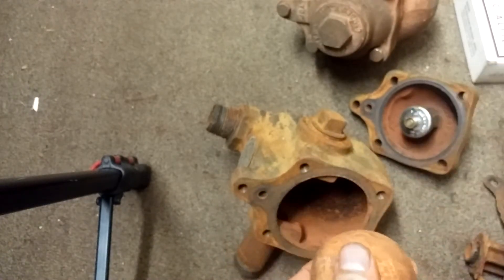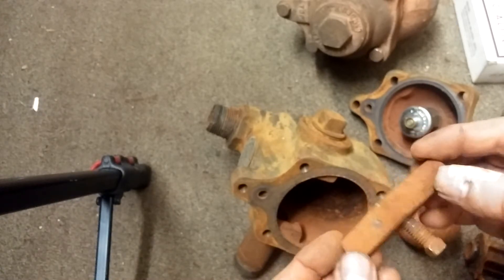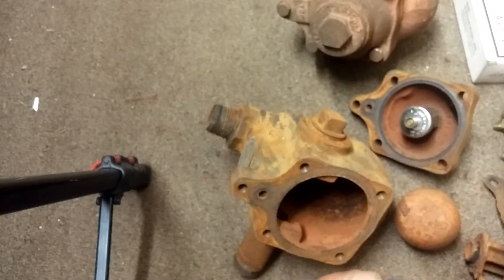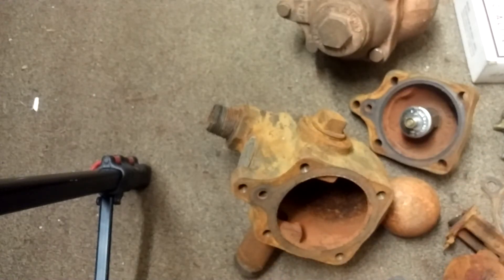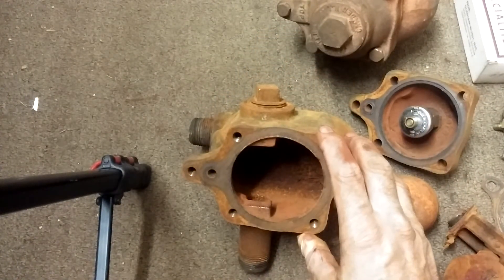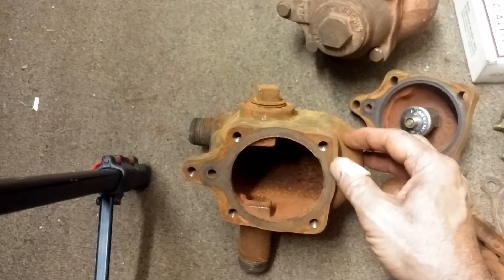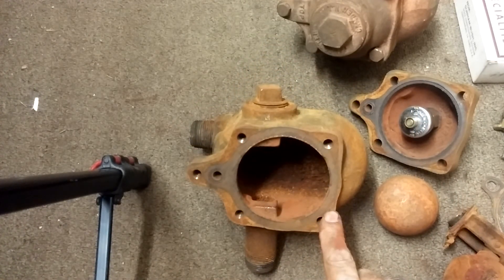Sometimes these OEM kits are a little shy. You can find some OEM kits with gaskets and crush washers. This would be hard to duplicate if that broke off — you might have to drill that out, but not impossible. I don't think it's going to be a good candidate for rebuilding unless this was surrounded by asbestos, or they put it in and built the building around it, like they've done in some situations I've dealt with. You gotta do what you gotta do. This presents some challenges, but I believe they can be overcome.